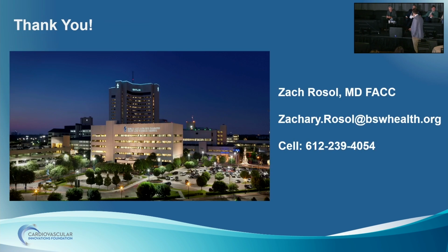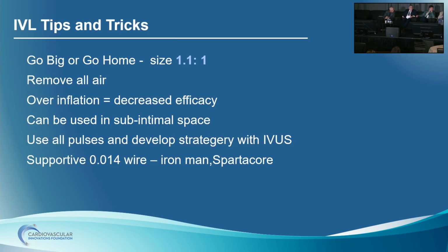It just bears mentioning, though, that the larger devices, the L6 devices, do go over an 018 wire. Yes, that's true. And especially for these larger devices like the iliacs and the aorta, it is nice to have that more supportive wire. Right. The M devices and the S are still 014.